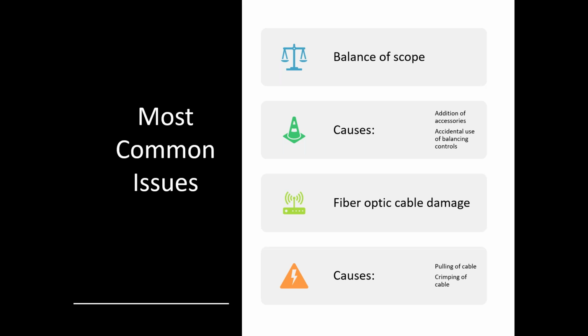Take this other end and run it through the eyepiece, and you'll point and it'll show you a circle, and all of the fibers that are broken will be blacked out. So if you've got a fiber optic cable that is 50% blacked out, you've got a bad fiber optic cable. So that's one way to check it in the field, kind of easy to do. Another thing would be if the cable has been pulled out or it's not actually seated into the head far enough or correctly, that can cause light transfer issues as well.